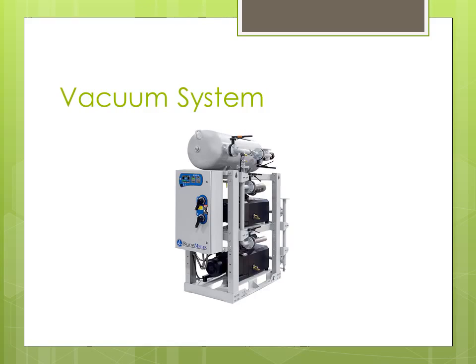Vacuum systems, similar to medical air, being that they're pumps and motors and storage tanks, have one other very interesting special consideration you have to be very mindful of, depending upon what type you have. If you have a water-cooled system, obviously if you were to lose water in your building for any reason, then you could lose your vacuum system. And sometimes folks don't realize that they can lose vacuum.